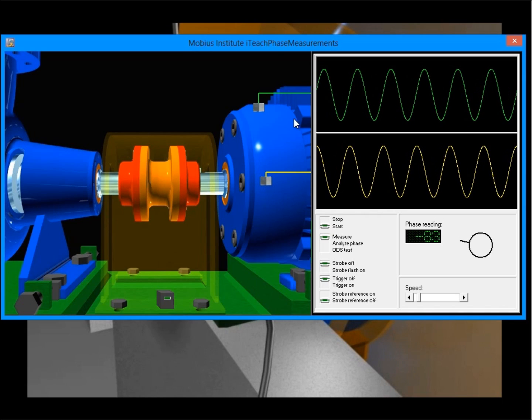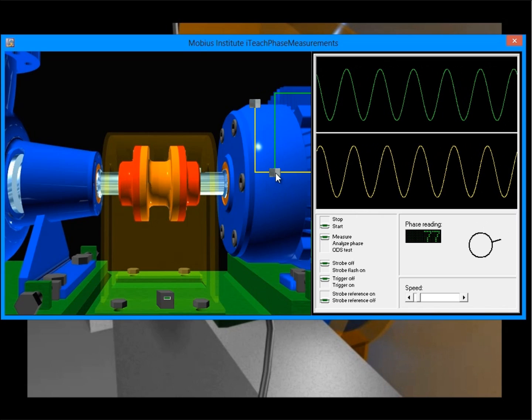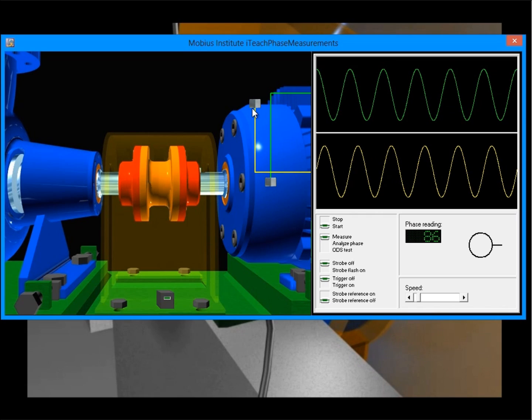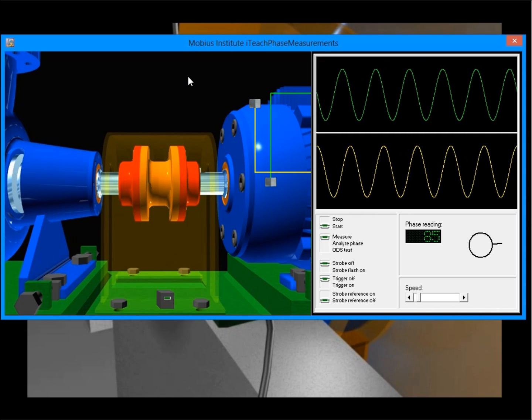Instead we can use two accelerometers in a two-channel analyzer and do the same sort of thing. We can see a 90 degrees phase shift. It's easier to do this way, we don't have to stop the machine.